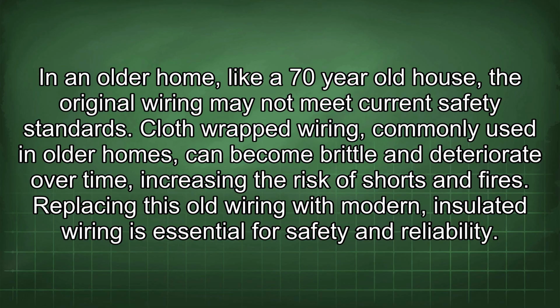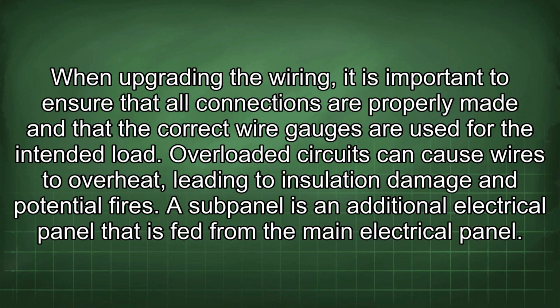In an older home, like a 70-year-old house, the original wiring may not meet current safety standards. Cloth-wrapped wiring, commonly used in older homes, can become brittle and deteriorate over time, increasing the risk of shorts and fires. Replacing this old wiring with modern, insulated wiring is essential for safety and reliability. When upgrading the wiring, it is important to ensure that all connections are properly made and that the correct wire gauges are used for the intended load. Overloaded circuits can cause wires to overheat, leading to insulation damage and potential fires.